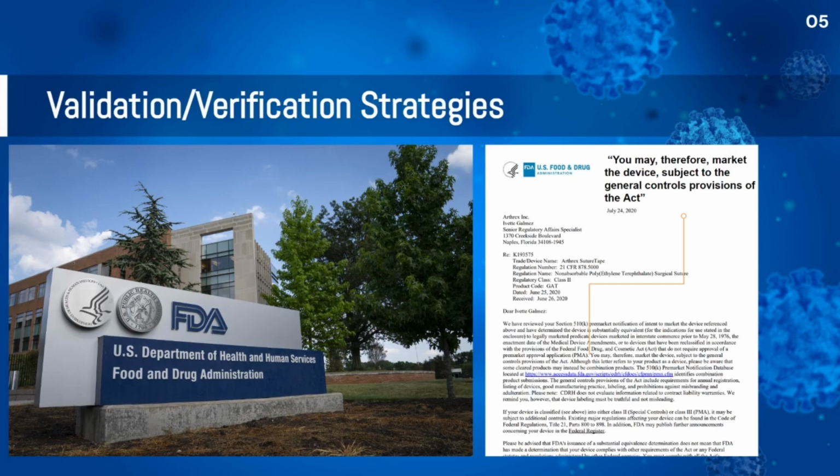After enough data has been obtained, how long the approval process takes depends on the medical device class, like stated during the concept stage, or if there are any existing predicates. Once the validation stage is over and the FDA regulatory approval process for commercial distribution is confirmed, you can prepare for a product's launch.